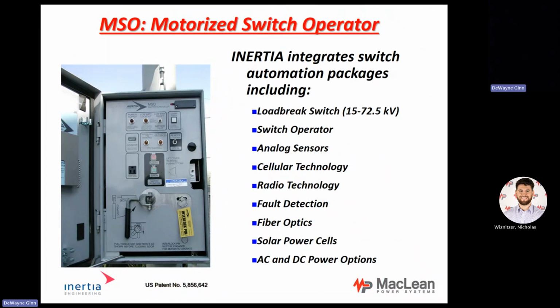There is a wind latch on the left at the bottom to keep the door from hitting you if you were out in the field trying to work on this, keep the door from hitting you all the way around. They're all SCADA ready. This depends on your communications modem. If you put cellular in it, radio, or fiber, it just depends on what you want. So all of the motor operators are ready to go on SCADA.